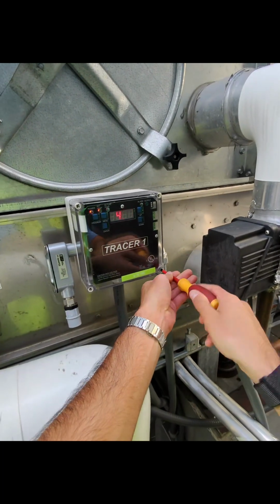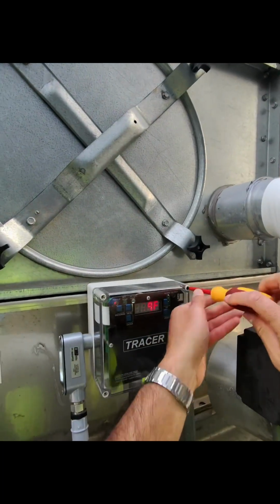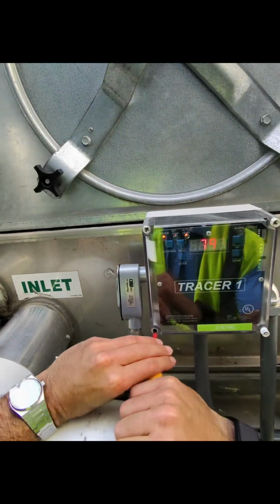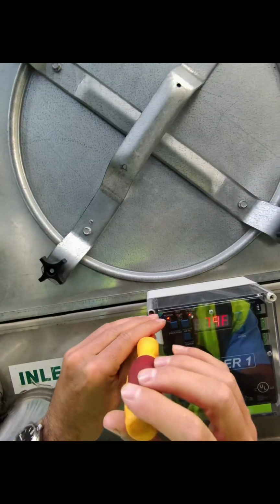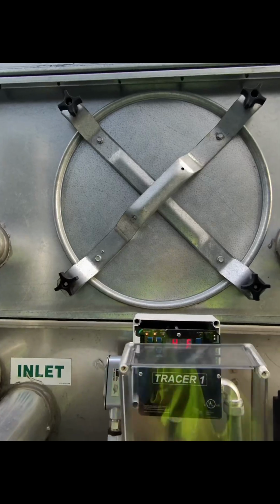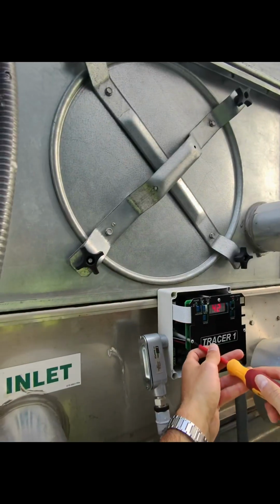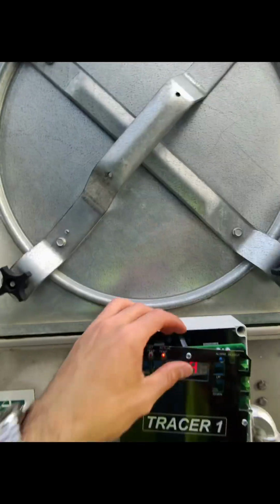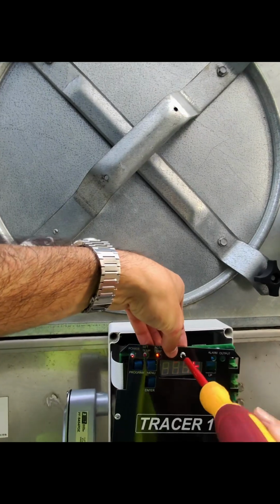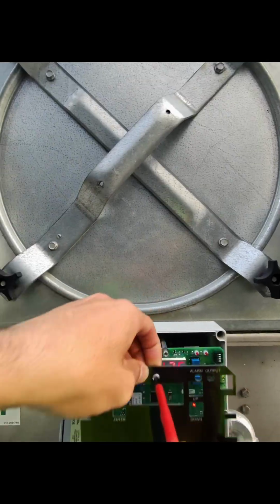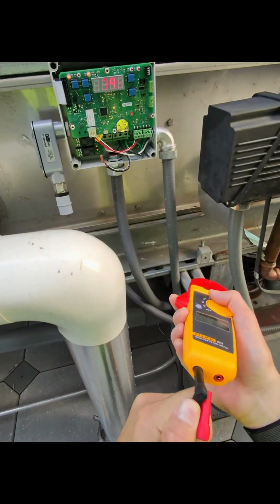In this video, we're going to go over a typical heat trace startup on a Tracer 1 heat trace controller. We'll start off by removing the clear cover, which is held on with 4 screws fastened at each corner. Behind that, there's going to be a black faceplate that has 3 screws holding that on. Put that somewhere safe so that you don't lose it.